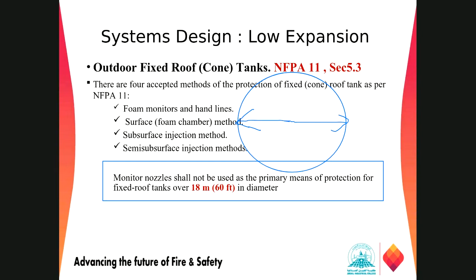Monitor nozzles shall not be used as the primary means of protection for fixed roof tanks over 18 meters in diameter. So if your tank diameter is higher than 18 meters, we cannot depend on hand line firefighting tactics or foam monitors. In that case we need a fixed foam protection system to inject foam into those areas and suppress the fire.